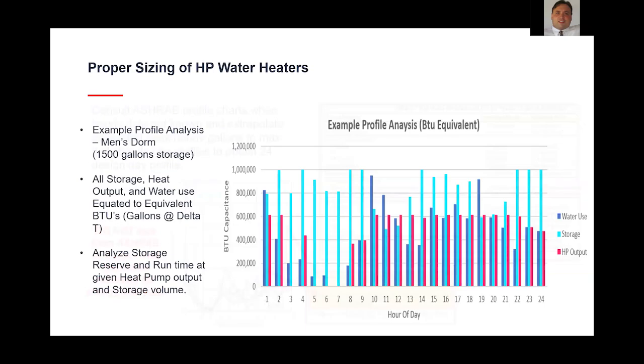a profile. And so you can start applying these profiles, looking at heat pump output capacity that you have available, and potential storage volume that you think you could fit into the occupied space, and you can start to analyze this. And you could do this in a manual method, or with an Excel-based type tool. And again, the goal is to look at this at least over the course of 24 hours, preferably over more than one 24-hour period because of that carryover effect, and analyze basically total net system capacitance, if you will.